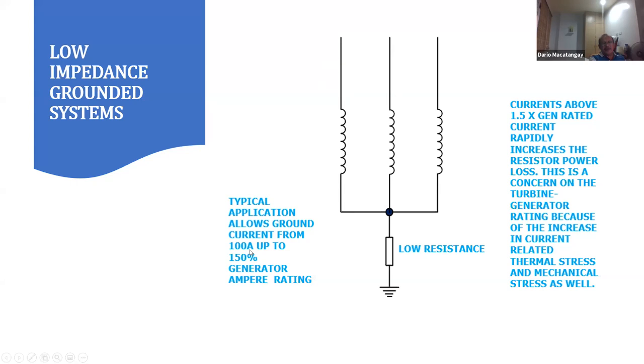If your CT ratio is very high, for example 2,000:5, that relates to a 400:1 CT ratio. So 100 amps divided by 400 is only 0.25 amperes in the relay. That is very small. Sometimes you cannot get good sensitivity, and you need to get it higher. A lot of times it might not work, but sometimes it will.